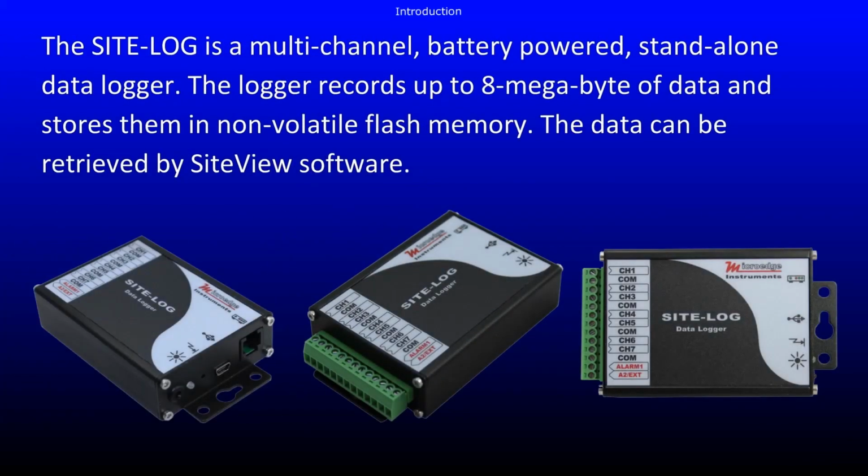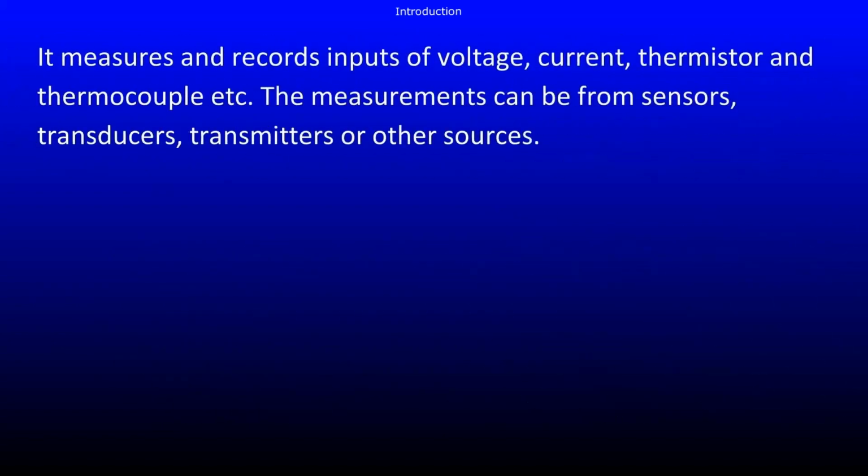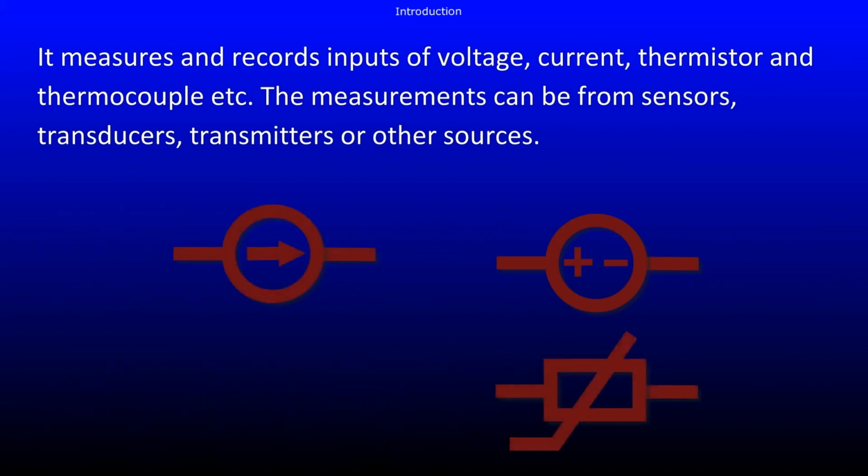The logger records up to 8 megabytes of data and stores them in non-volatile flash memory. The data can be retrieved by SiteView software. It measures and records inputs of voltage, current, thermistor, and thermocouple, etc. The measurements can be from sensors, transducers, transmitters, or other sources.